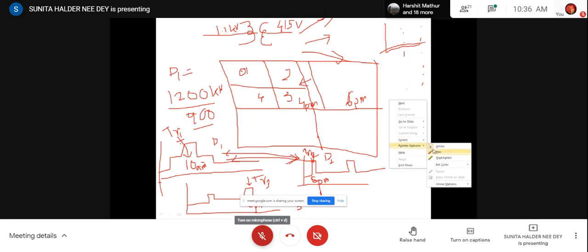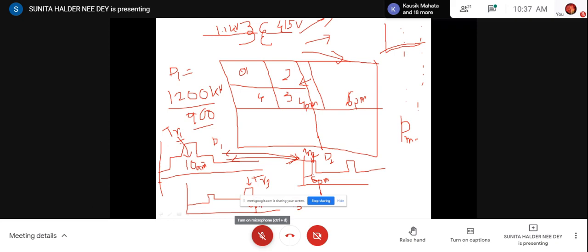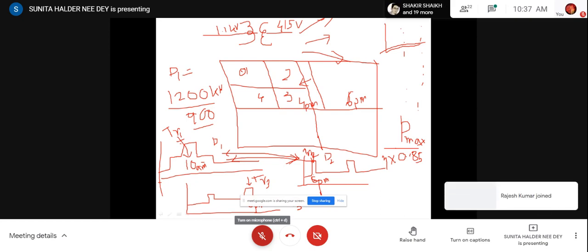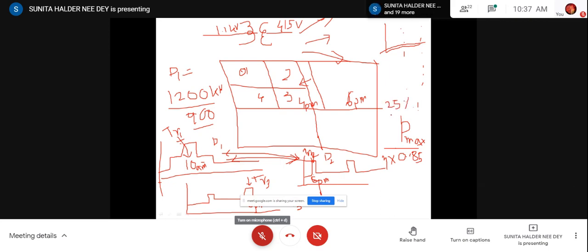Can you see the screen now? So if you get the maximum demand P max, then you can convert it into kVA by dividing it by the power factor. Say the power factor is 0.85. Then if this power is required at the output of the transformer, you divide by efficiency to find the transformer input, or transformer size. This is the required load at this time, but there is always the possibility of load increase in future, and the consumer will not inform you. So for that we take 25% extra for security, so that if the load increases by 25%, it will not hamper our distribution system.